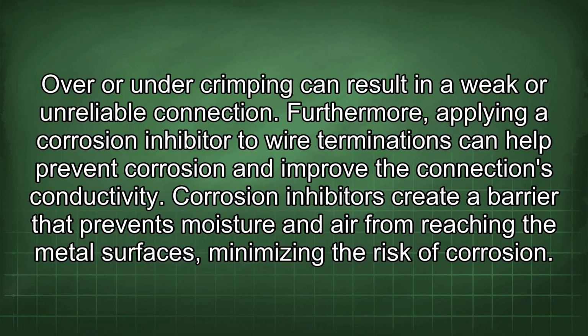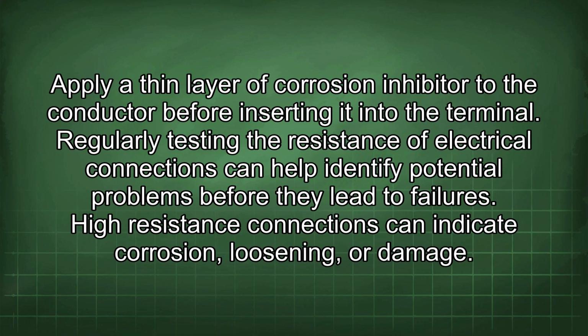Furthermore, applying a corrosion inhibitor to wire terminations can help prevent corrosion and improve the connection's conductivity. Corrosion inhibitors create a barrier that prevents moisture and air from reaching the metal surfaces, minimizing the risk of corrosion. Apply a thin layer of corrosion inhibitor to the conductor before inserting it into the terminal.